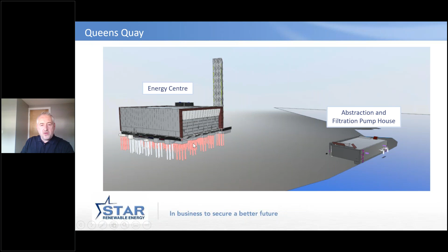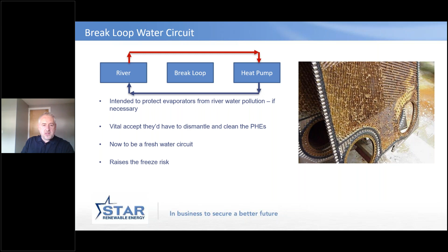Now, some people, when we start the conversation, say, well, I want to put a break loop because I don't want my heat pumps touching the river water because that might damage them. And we try and point out that by putting a break loop, you've got a 2 or 3 degree temperature difference. And what if you made a heat pump that was slightly better and was able to take that water directly into the heat pump? The impact we would get by having no break loop is a heat pump that's operating 2 or 3 degrees warmer. Now, you might say 2 or 3 degrees, why bother? And that's the point of the next couple of slides, is to show why that's significant.